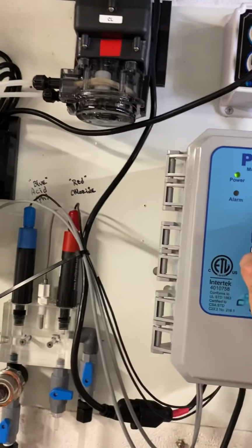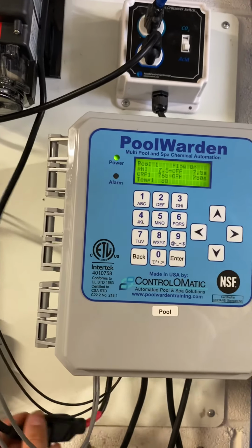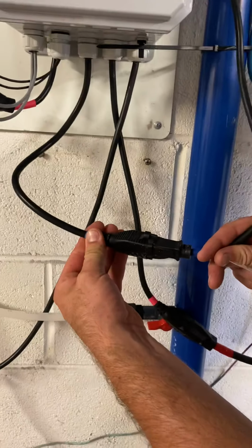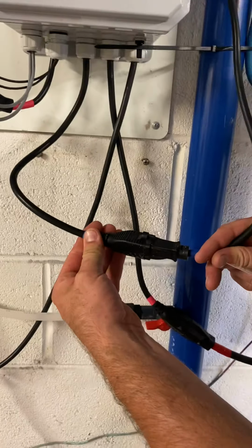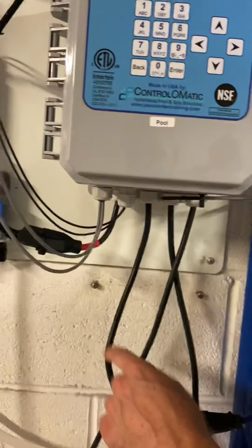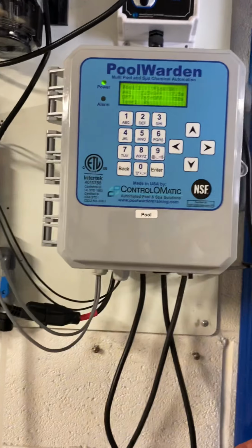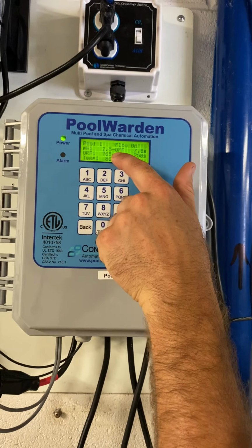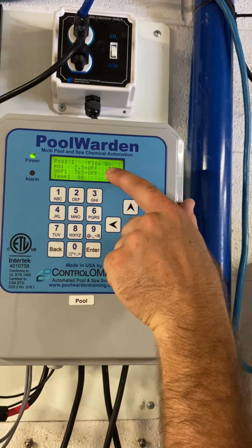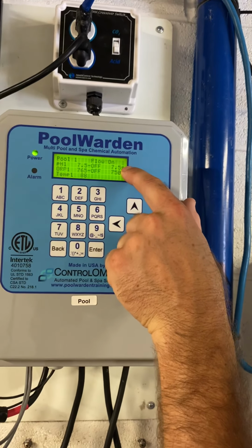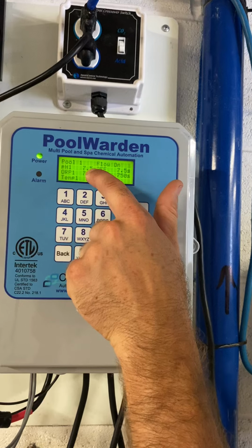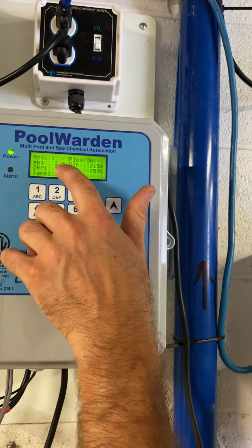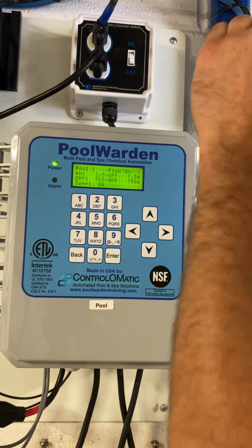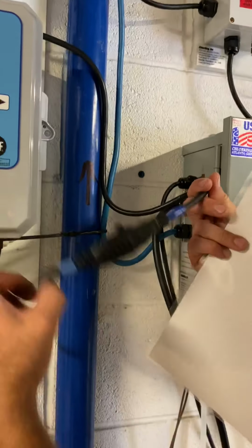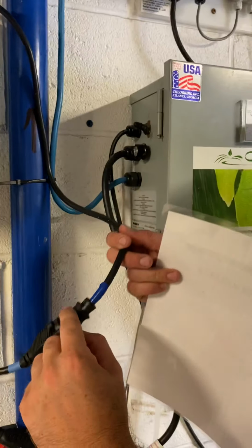Over here, where it says off, that tells you what the relay is doing, okay? And that's what these two pigtails are. So blue is for your pH, red is for your chlorine. So when it needs to call for either product, it sends power to either one of these pigtails, which will activate a pump. Right now, both are off. When we jump over here, this is our set point. So 7.5 S is for set point. You can see that we are at our set point, so nothing's going to feed until that number goes up. And then it's going to activate this relay inside here, send power through the pigtail, then going up to this device.